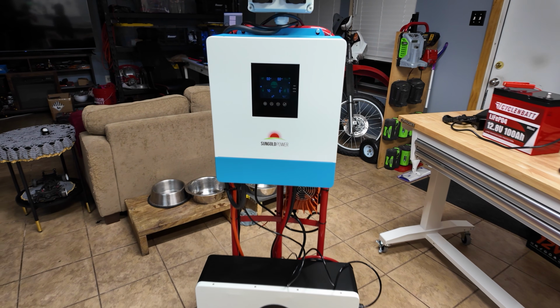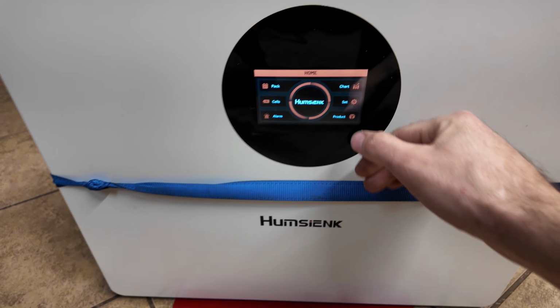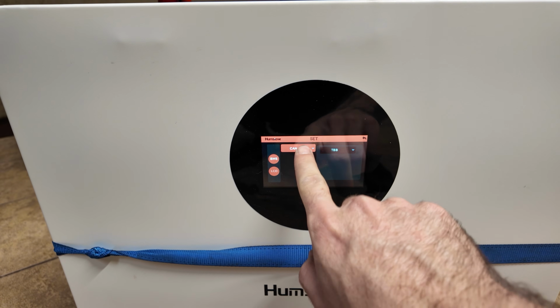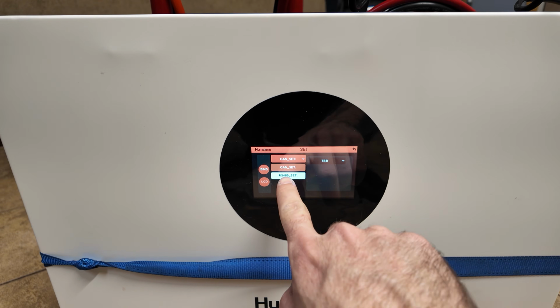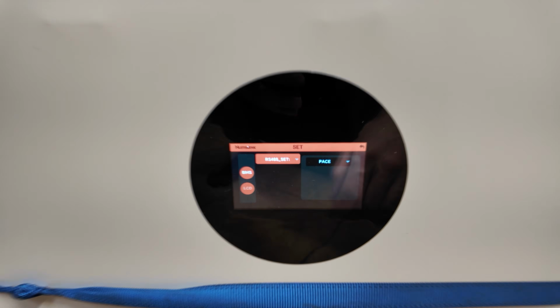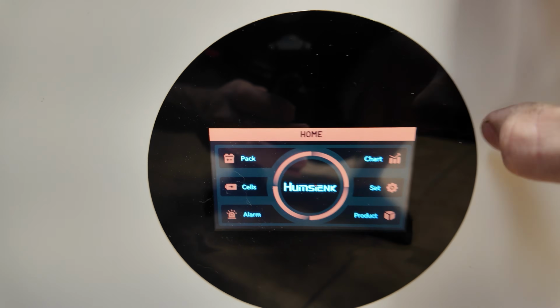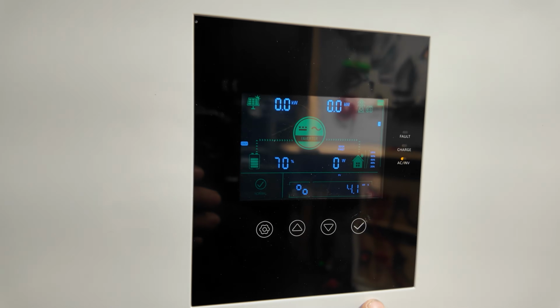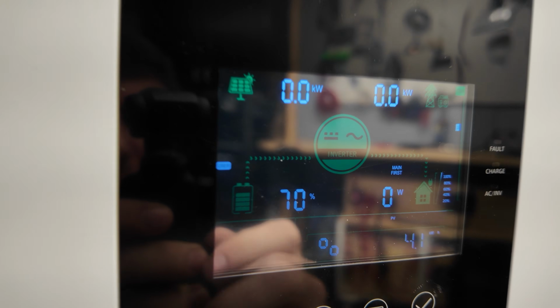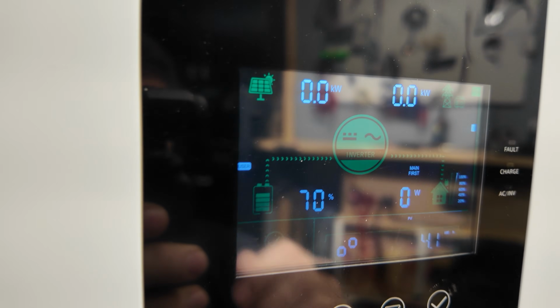So I was able to get the communication feature to work. I did have to go in here to set, and make sure the RS485 was set up. All I did was hit 485 set, and I just left it on pace. I left that alone because I didn't have an option for SunGold. If we come up here to my inverter, as you guys can see, it's showing battery percentage, which means we are communicating. So that's really good to see.